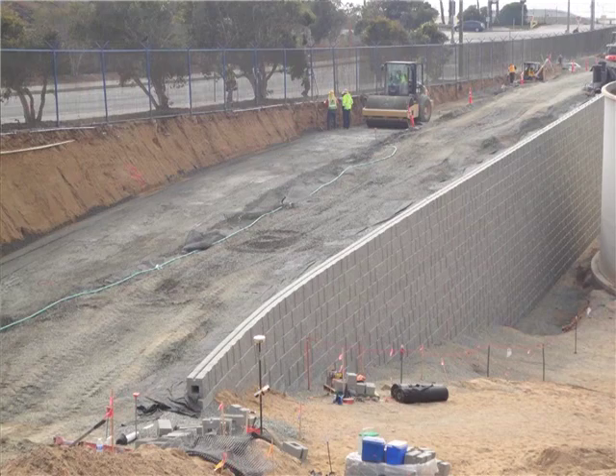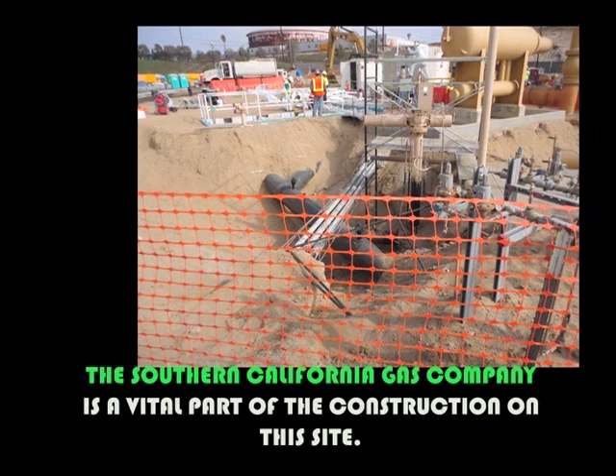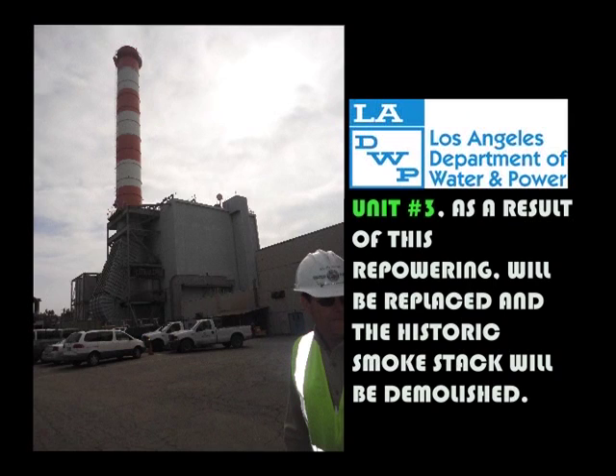We're actually aware that government mandates and some environmental concerns have necessitated part of this repowering of Scattergood. Could you talk about that? Some of the constraints and government mandates include the elimination of ocean water for cooling, improved efficiency, and reducing emissions. For example, this project will have a dry cooling system, which is basically a radiator, and we will not have to use the ocean for cooling. This technology is a lot cleaner and more efficient. It uses a combined cycle, which makes this equipment consume less fuel for the same amount of power produced from the current equipment.